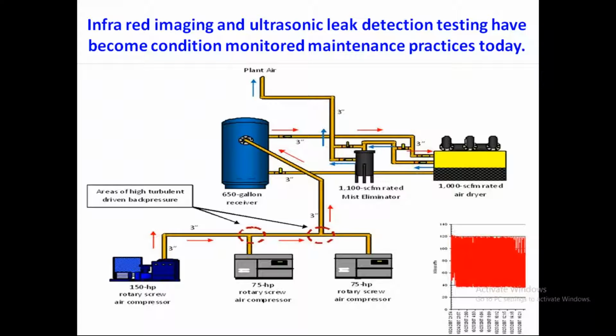In the distribution, it is different. Around 15 meters per second, it can go higher also. But on the compressed air header, I will suggest you go for a compressed air flow meter to monitor the velocity, because all the GI pipes and all the MS ERW pipes, electric resistance welded pipes, get totally corroded and scaled inside. Instead of a 4-inch pipe, you will have only a 3-inch pipe inside. Automatically the velocity will go up, the distribution loss will definitely increase, and the pressure drop end to end will definitely increase.